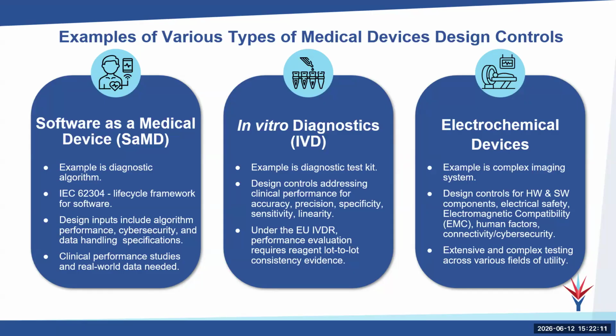And in vitro diagnostics, a diagnostic test kit, those are one of my favorite things to work on. With design controls, you're really looking at the clinical performance. Sensitivity and specificity is a balancing act. You get one up, the other goes down. You've got to balance there. And accuracy, precision, and linearity are all the clinical performance that you need to prove in the actual samples that will be used for the test kit's design. Under the EU, the IVDR has very specific performance evaluation requirements. It also requires reagent lot-to-lot consistency, which is kind of a unique thing there.